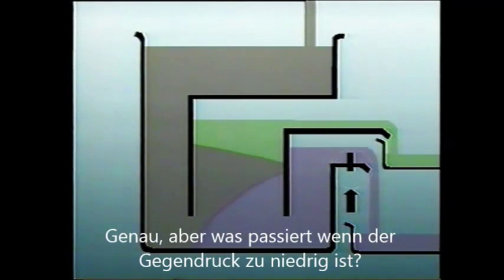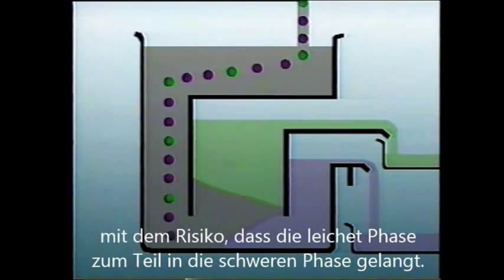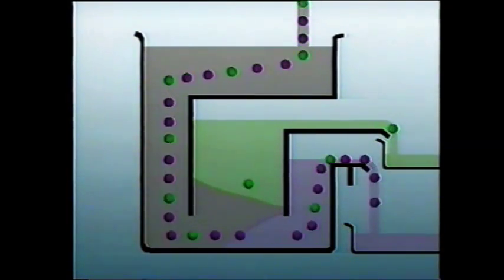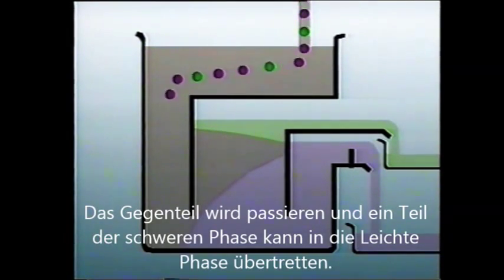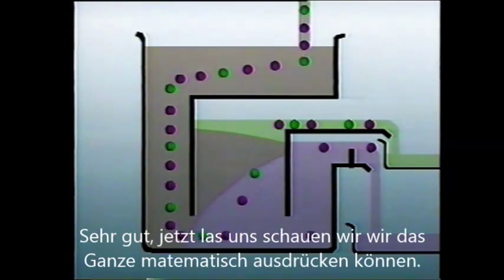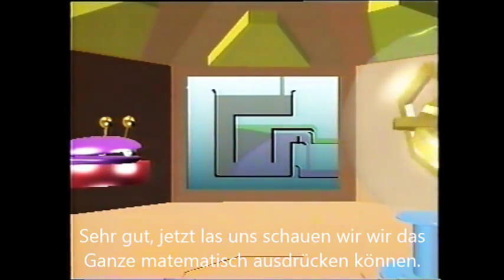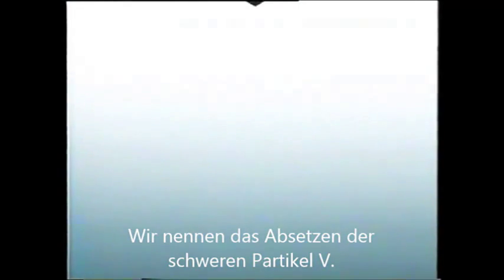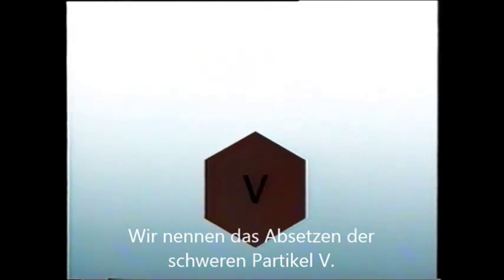But what would happen if the dam is set too low? The position of the interface moves lower, which means there will be a risk of some of the light phase escaping with the heavy phase. And if it is set too high? The opposite will happen, and some of the heavy phase may escape with the light phase. Now let's go back and see how we would express the whole thing mathematically. We call the settling velocity of the heavy phase particles, or globules, V.